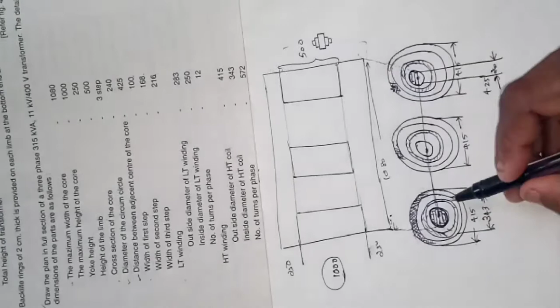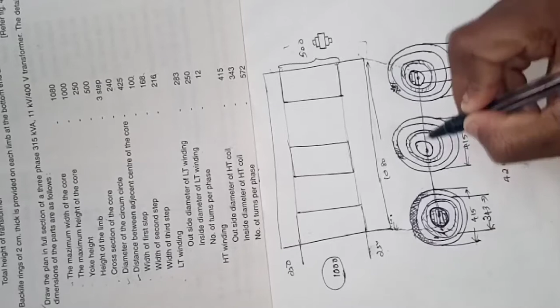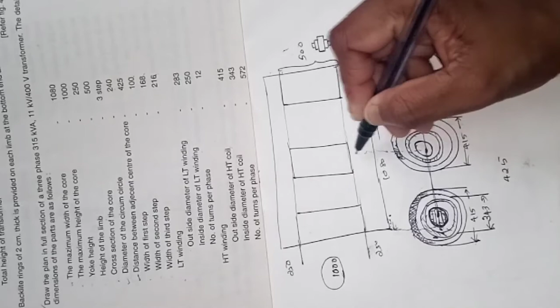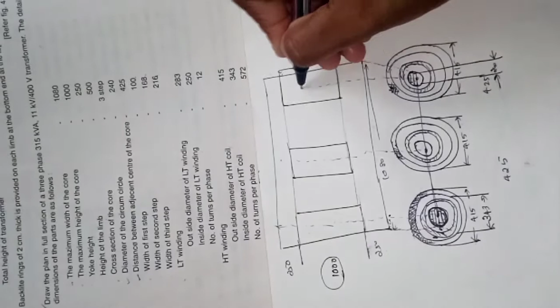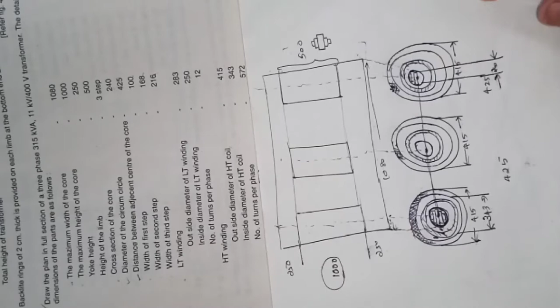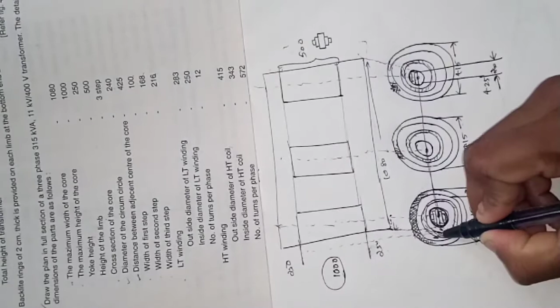And after this there will be insulation, then low voltage winding, then insulation, then high voltage winding. Here also this is the circumcircle of the core. From here we can draw like this. This is the center of the limb. Using scale you can definitely and correctly draw it, and you can extend the low voltage winding to the top side. So this is the low voltage winding inner side diameter, low voltage winding outer side diameter, high voltage winding inner side diameter, and high voltage winding outer diameter.